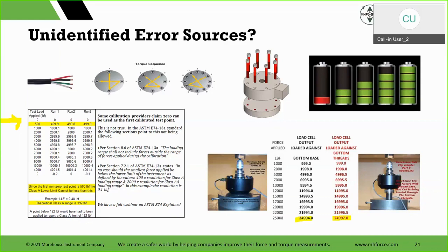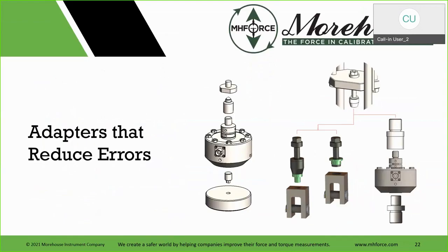Using different size adapters than what was used, loading against the bottom thread, temperature effects on a non-compensated force instrument, using electrical instruments that were not used during calibration, excitation, voltage, cabling, shielding, all kinds of different error sources that are really here. And the main thing is that there are adapters available.